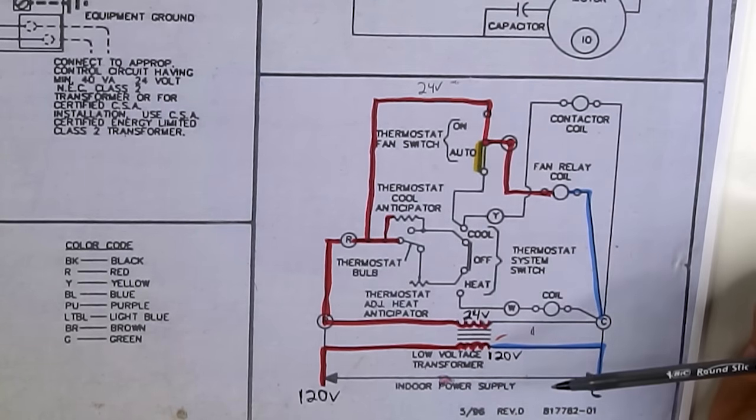When the discharge temperature switch goes up and interrupts the circuit, it means the contactor plunger goes up, which opens the contacts, interrupting the 240 volts feeding the unit and turning everything off. All of these switches are normally closed in a normally operating system — they only open if there is a problem. Another new component is this little board labeled CTD, which stands for compressor time delay board. Its purpose is to prevent the compressor from short cycling. This little symbol is the symbol for a time delay switch.